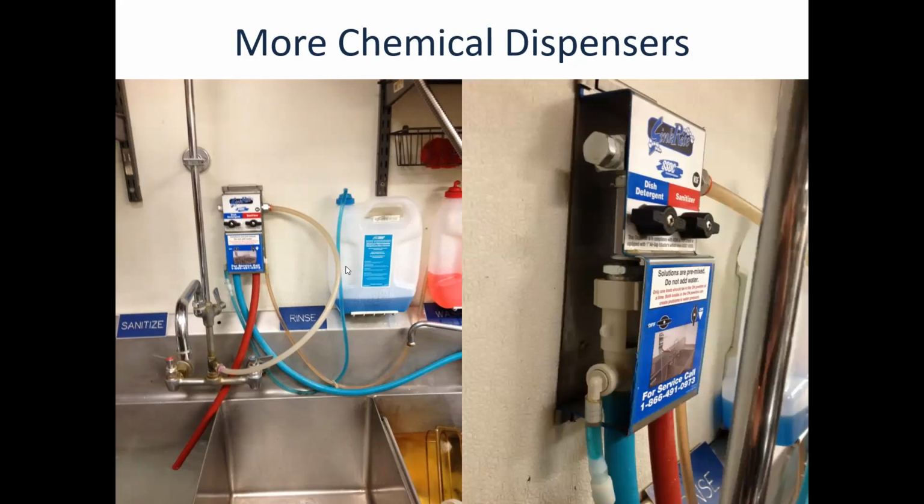It does not need a wasting tee because there is not an atmospheric vacuum breaker included here, and there's not a threaded faucet that we could be attaching things to. So at least in this picture, we don't see the atmospheric vacuum breaker, but because it does not have that threaded hose bib or a threaded faucet, they cannot be attaching valves downstream of it. So that's why things are okay.